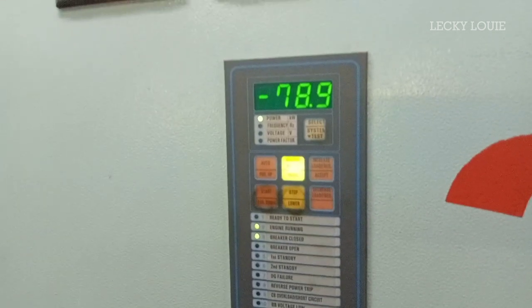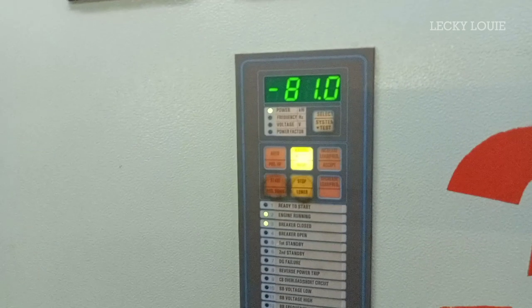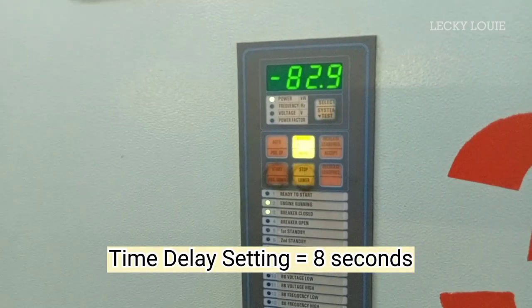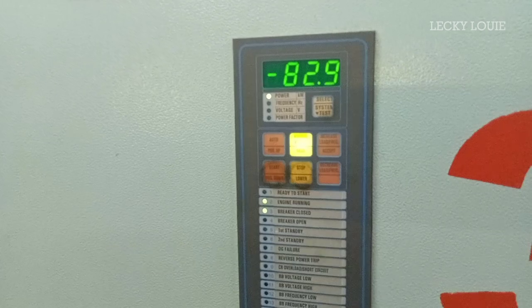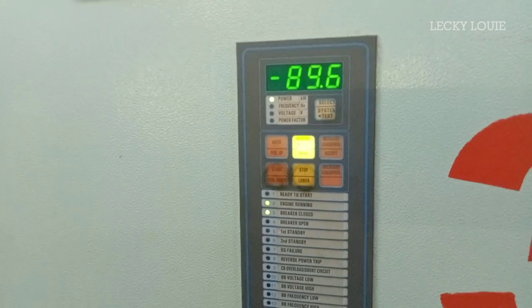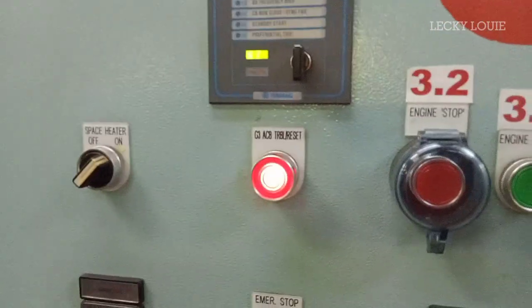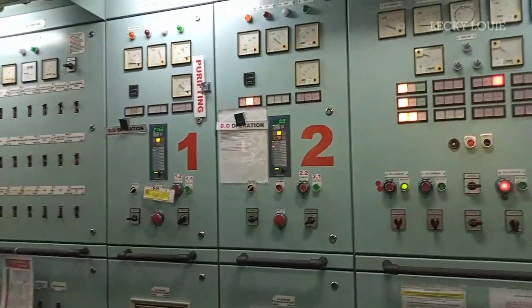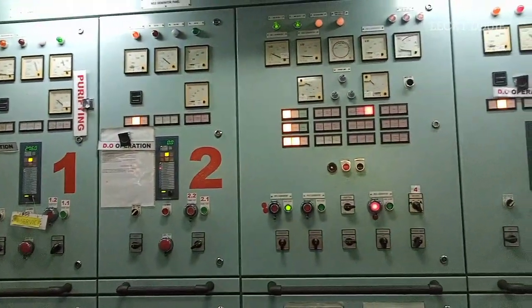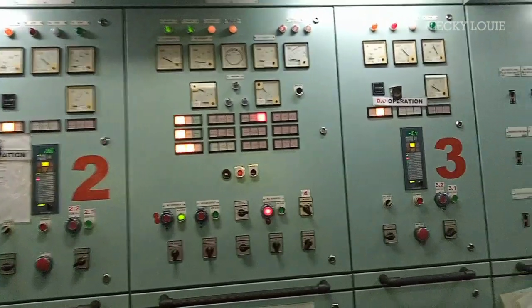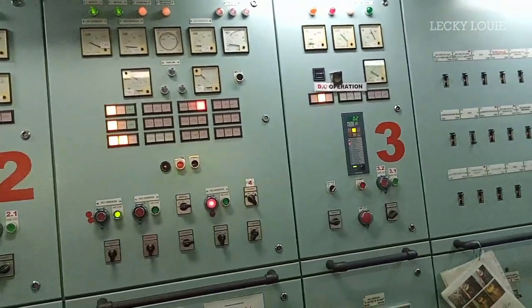The second factor is the rated time delay setting. Our reverse power time delay setting is 8 seconds. Meaning, if our generator runs with a negative 75 kilowatt load within 8 seconds, the reverse power protection will activate and automatically disconnect the generator air circuit breaker, which prevents the generator motoring. I think we now have an idea about the reverse power protection, and we are now ready for the actual testing of the reverse power trip alarm.